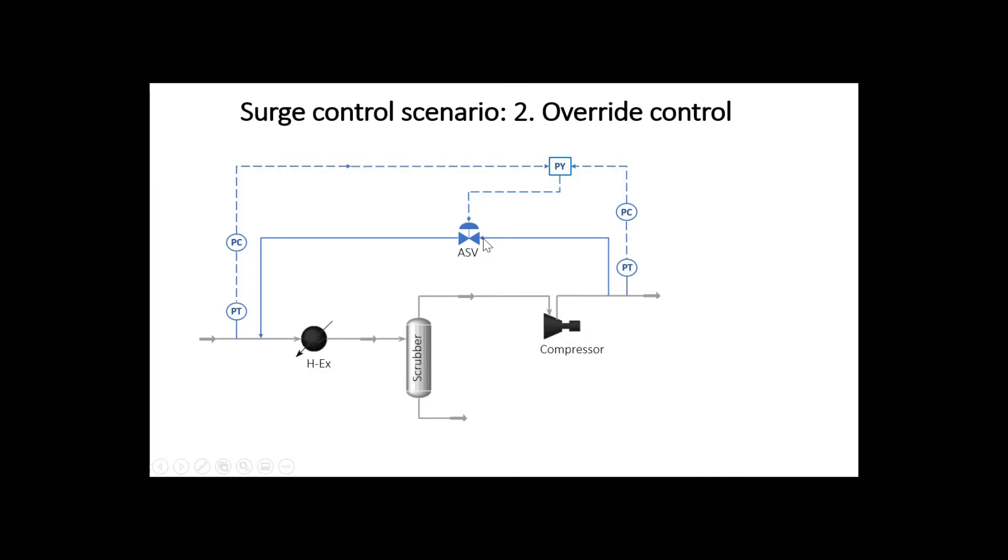Let's imagine pressure in the suction line decreases and pressure in the discharge line increases somehow caused by other disturbances. The discharge controller requires X percent opening in the anti-surge control valve, while suction controller requires Y percent. Here the override system, in this case the low selector, selects the lowest error, considers the worst case scenario and eventually satisfies both controllers.